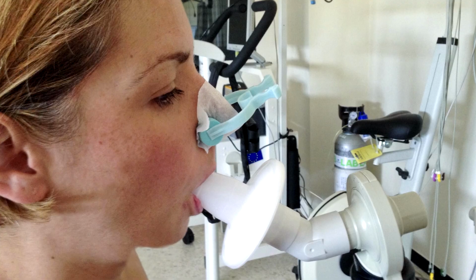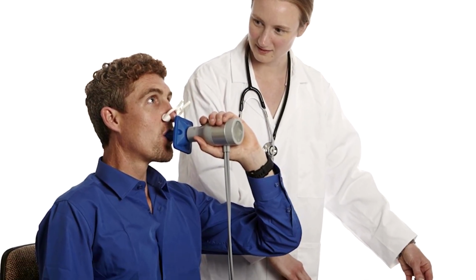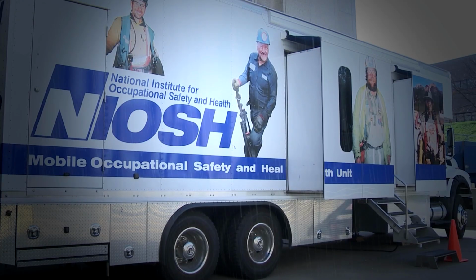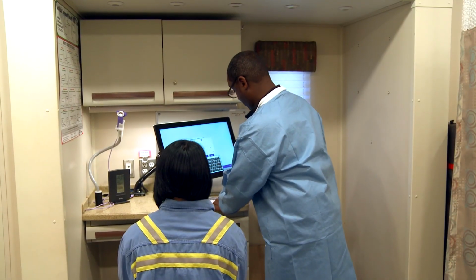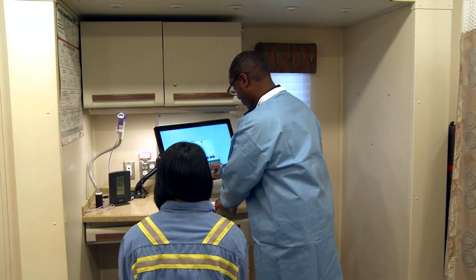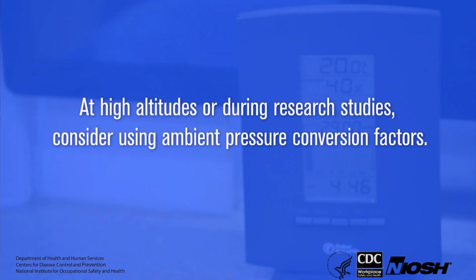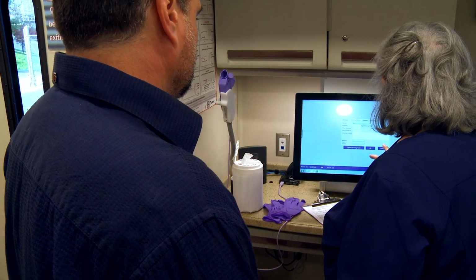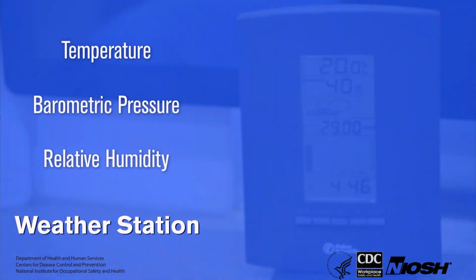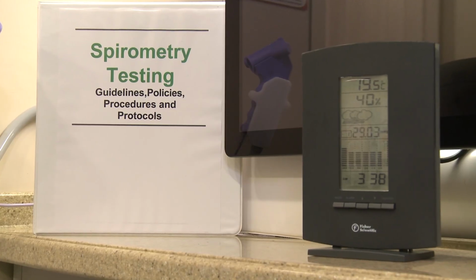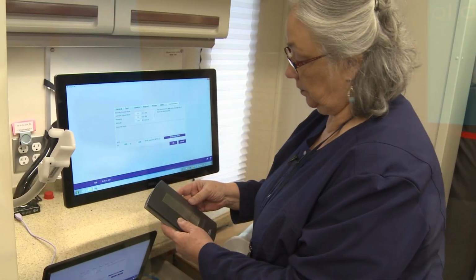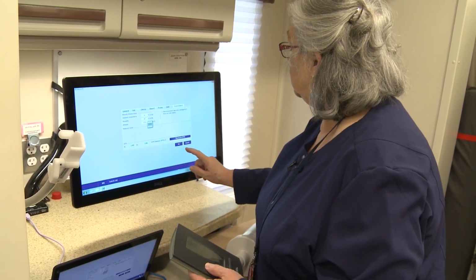Depending on the type of spirometer, manufacturers may preset their conversion and tell the consumer that it is not necessary to correct for ambient conditions. Regardless, NIOSH strongly recommends that ambient temperature and pressure be entered and reported during spirometry testing. At high altitudes or during research studies, consider using ambient pressure conversion factors. When conditions change, be sure to re-enter the new values into the spirometer. A high-quality thermometer and barometer are important tools that enable a technician to monitor the testing area for changes in ambient conditions that can affect spirometry results.